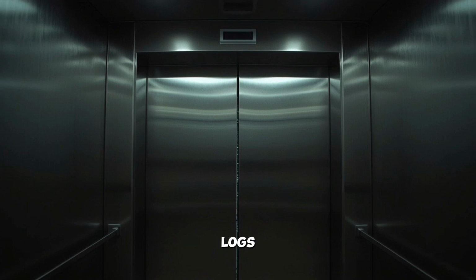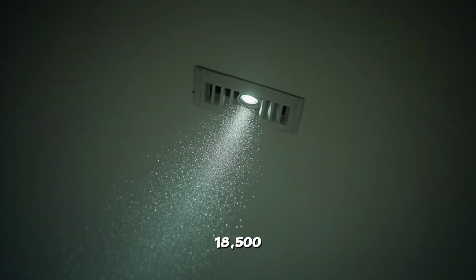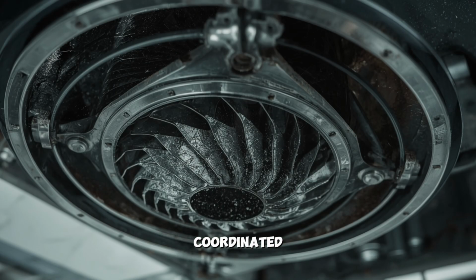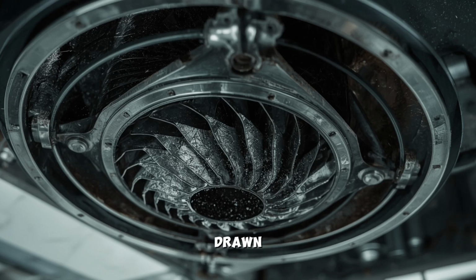The building management system logs from this period show that supply air volumes to the lobbies had increased incrementally over the preceding 2 hours, with total airflow rising from the standard 12,000 cubic feet per minute to nearly 18,500 CFM in the 6th Avenue building. The increase occurred through a series of small adjustments made by zone controllers responding to temperature sensor readings that indicated cooling demand, though outdoor temperatures were recorded at 41 degrees Fahrenheit with light winds from the northwest. The dampers serving the upper floor return air pathways had simultaneously begun to close in coordinated response to the firmware's interpretation of reduced occupancy signals, restricting the volume of air being drawn back through the vertical shafts and creating a hydraulic imbalance within the building envelope.